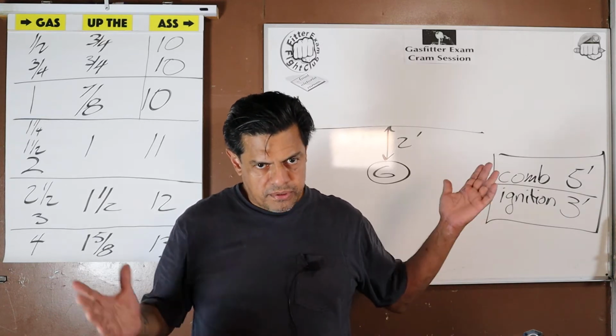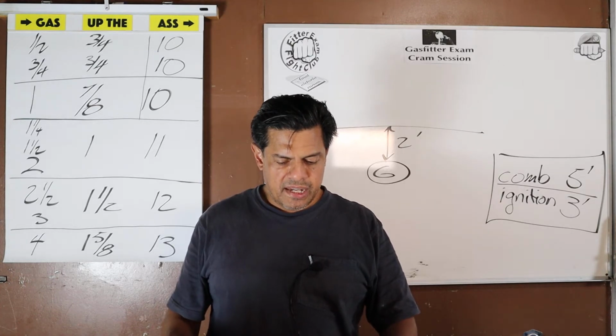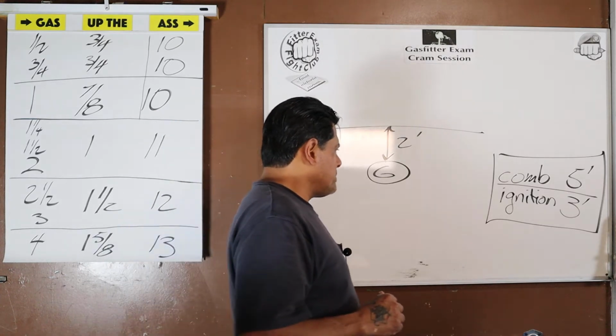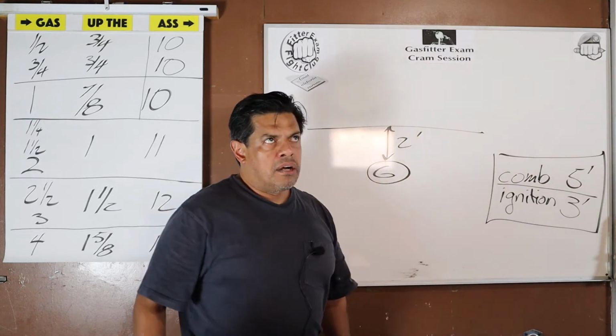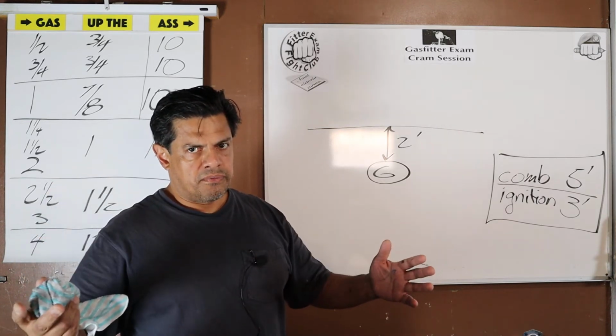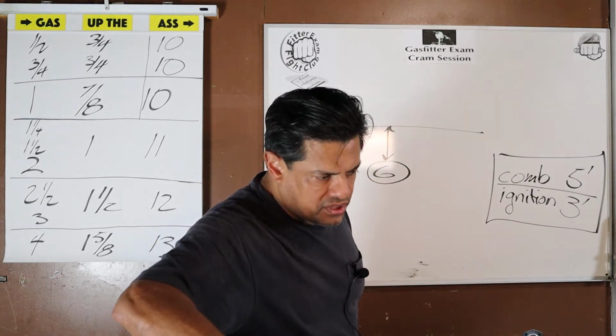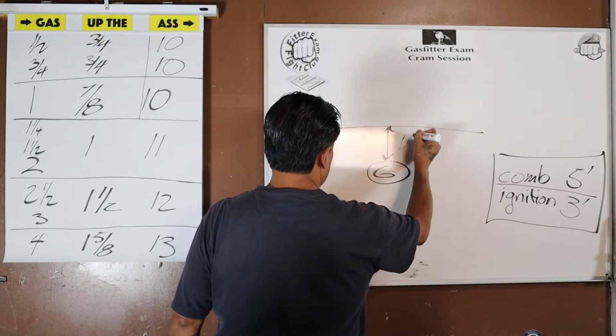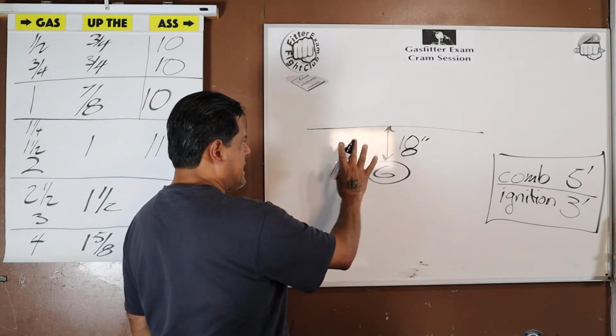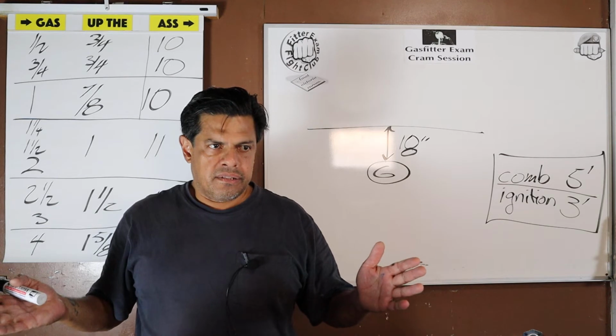Question 30. Now, of course, there are always exceptions. Gas piping may be buried not less than 18 inches below grade if properly protected and not located under a driveway. Properly protected means if we're going less than 18, we're generally talking about any loading stresses, freezing, the pipe is wrapped to protect against freezing. So we can decrease this to 18 inches. That's 1.5 feet, another number the code loves. We can decrease this to 18 inches or 1.5 feet if it's properly protected and it cannot be underneath a driveway.